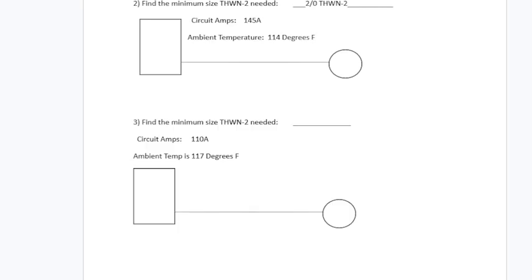So now that you have the method, you can try the divide one if you haven't used that one yet. Definitely going over to Table 310.16 and going, all right, what wires come closest to 110 but a little bit bigger? Let me start there and see if after I divide the correction factor into it, it can still hold.